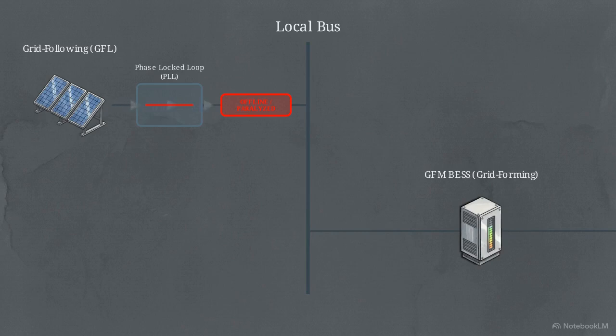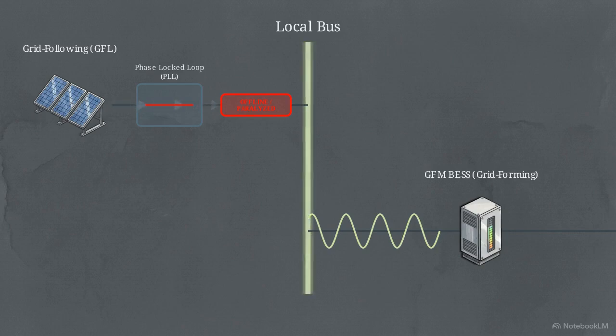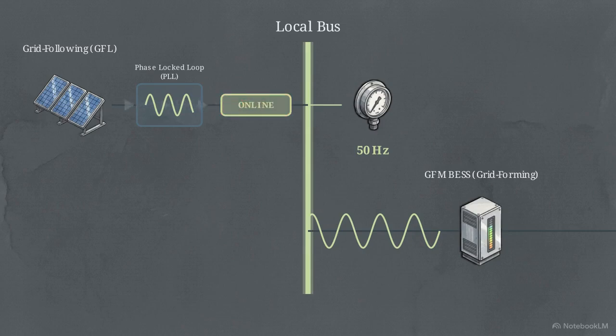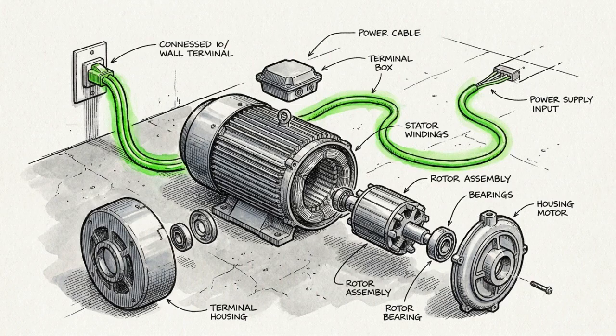True autonomy requires a grid-forming inverter. These act as primary voltage sources, creating grid parameters from scratch. This starts the black start process. The GFM autonomously energizes the local bus, establishing a steady 50 Hz heartbeat for the isolated network. Now, the paralyzed solar units detect that heartbeat. Their phase-locked loops lock onto the new frequency, transition online, and begin injecting power. Only after the solar generation is synchronized and supporting the battery can the heavy, critical motor loads be safely reconnected.